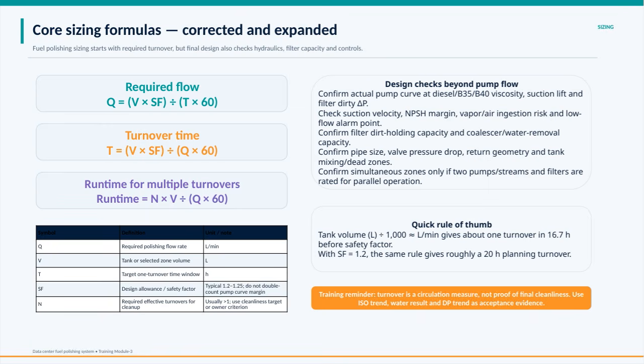Finally, remember that turnover measures circulation, not cleanliness directly. Always use ISO cleanliness trends, water content results, and differential pressure trends as evidence that polishing is effective. This comprehensive approach ensures your fuel polishing system is properly sized and performs reliably to maintain fuel quality.